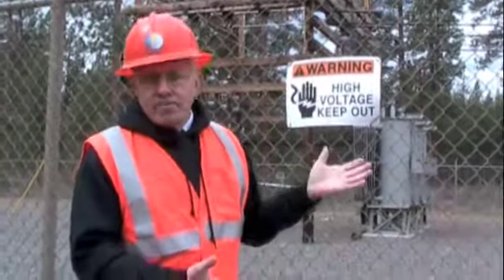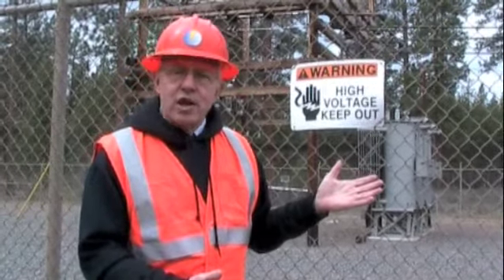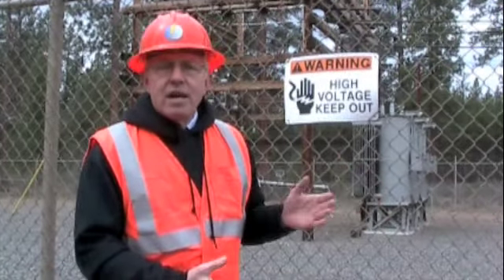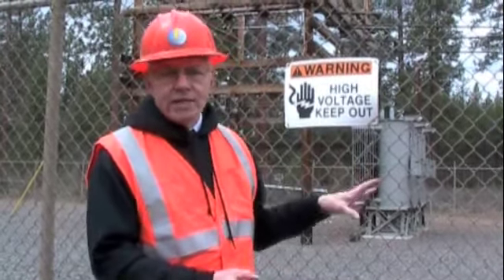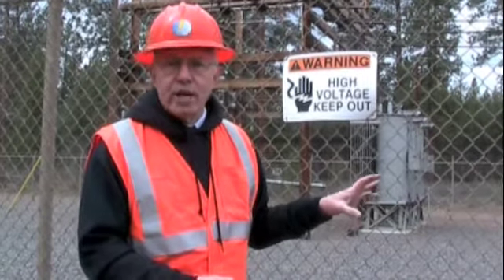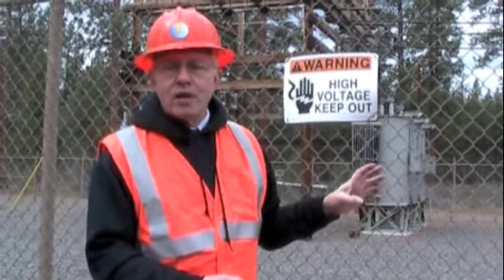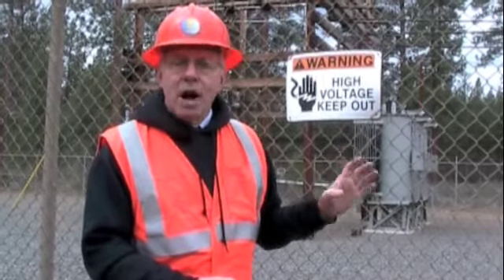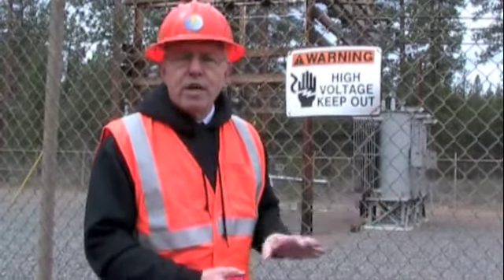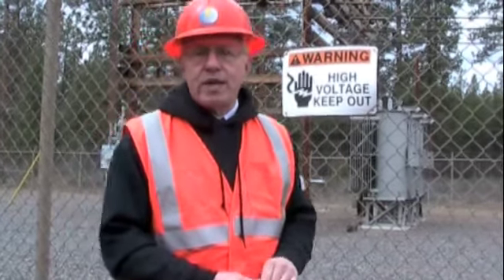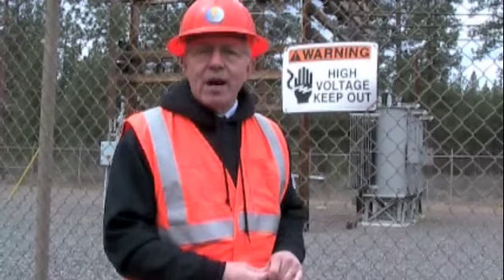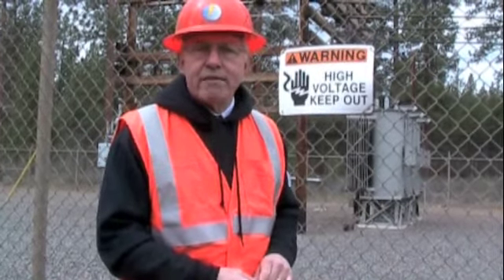This is the old substation. It's been here since 1995. It's inadequate for the load growth in this area. Also, it will only take 69,000 volts of electricity. The transformer is not equipped to take 115,000 volts, and that's what we want to upgrade to in the next 2 or 3 years, as soon as Bonneville Power Administration can start supplying that voltage.